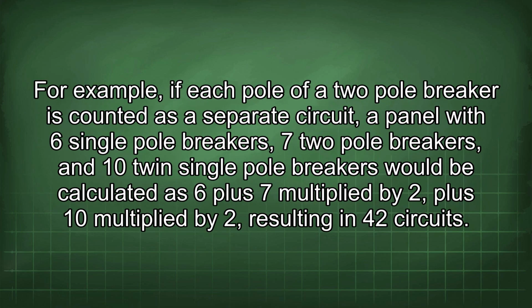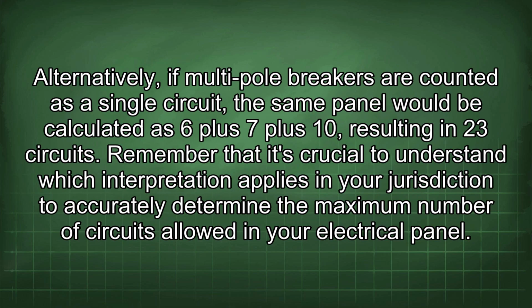For example, if each pole of a 2-pole breaker is counted as a separate circuit, a panel with 6 single-pole breakers, 7 two-pole breakers, and 10 twin single-pole breakers would be calculated as 6 plus 7 multiplied by 2 plus 10 multiplied by 2, resulting in 42 circuits. Alternatively, if multi-pole breakers are counted as a single circuit, the same panel would be calculated as 6 plus 7 plus 10, resulting in 23 circuits. Remember that it's crucial to understand which interpretation applies in your jurisdiction to accurately determine the maximum number of circuits allowed in your electrical panel.